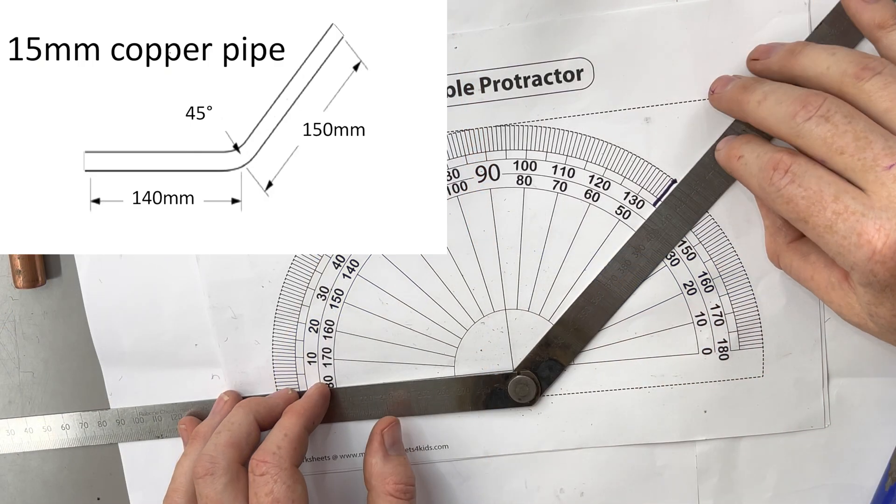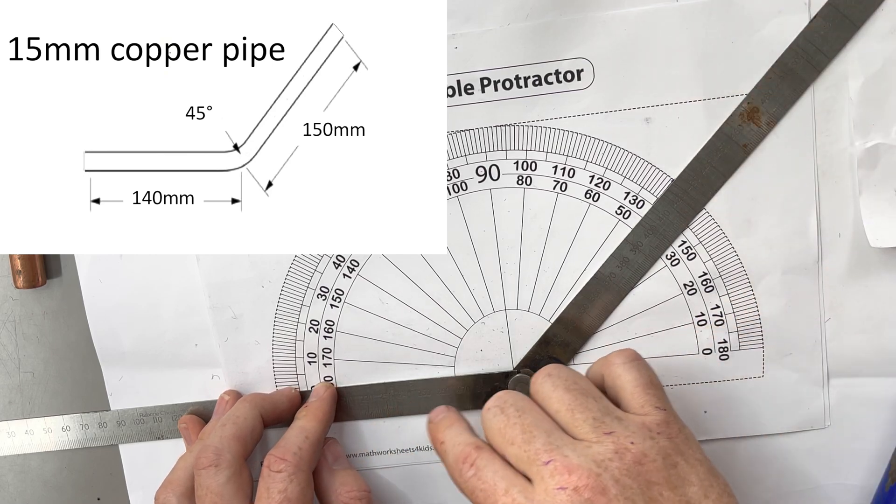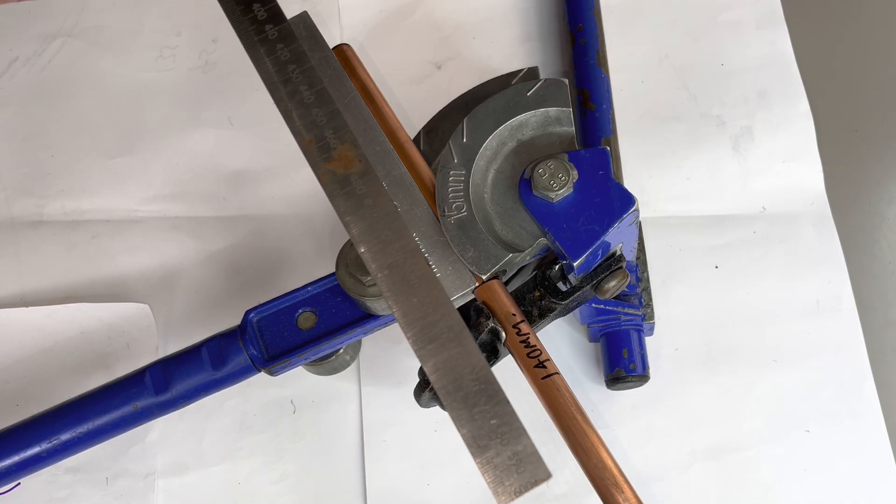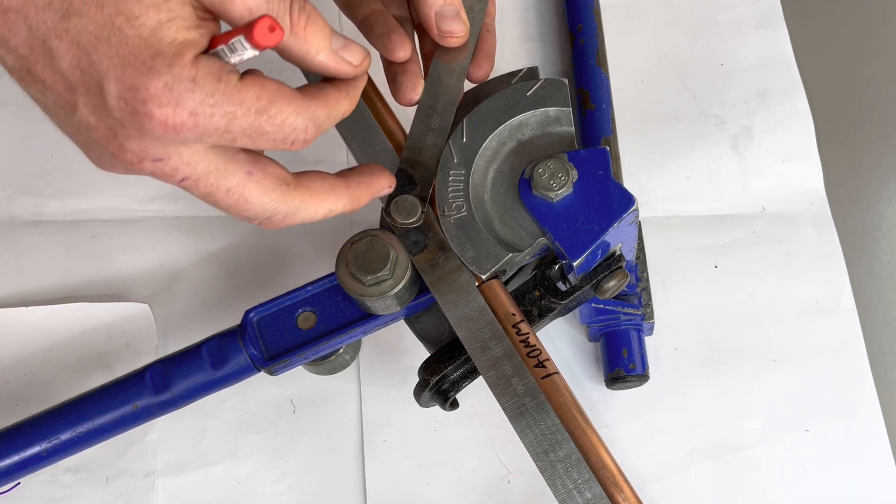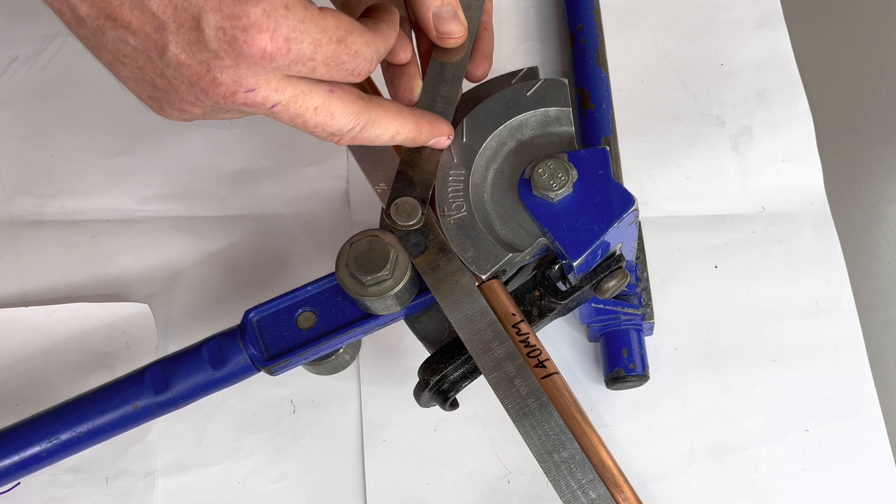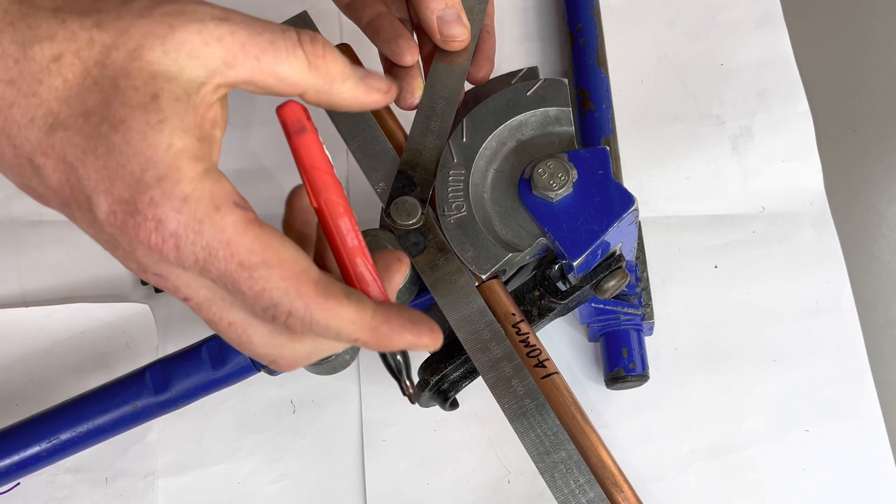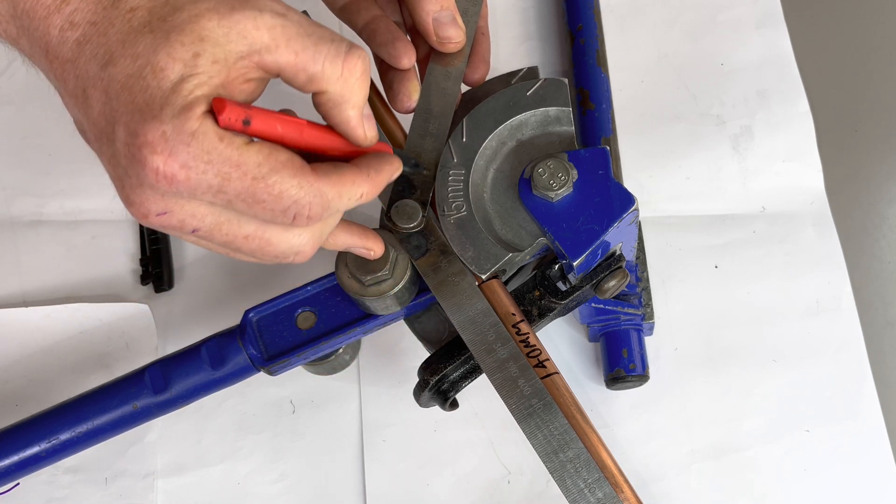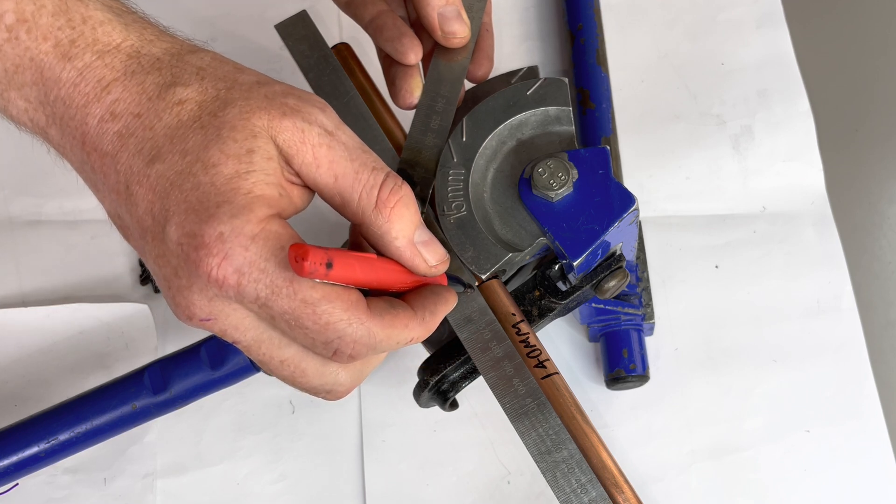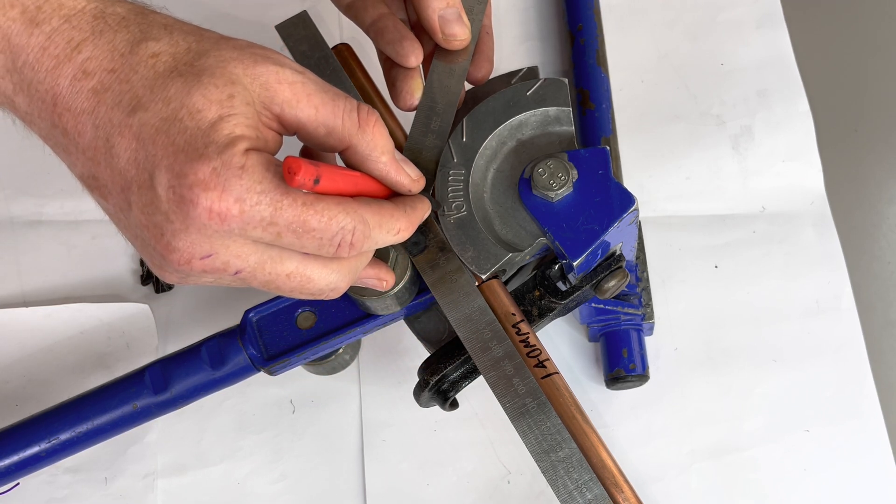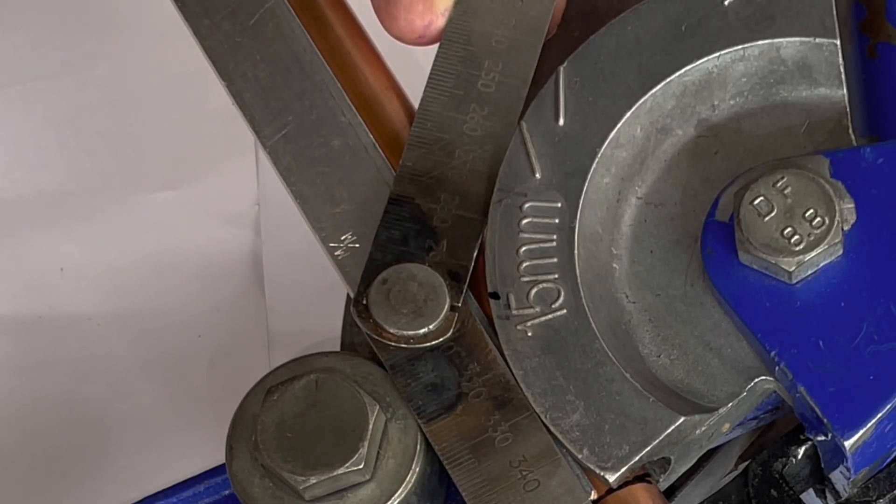Okay, using the folding ruler, set the angle to 45 degrees. Make sure it touches both sides of the former and it's also parallel with the pipe. So touching the former, touching the former, and parallel, which is here. And we then do a mark. This mark is the center of a 45 degree bend.